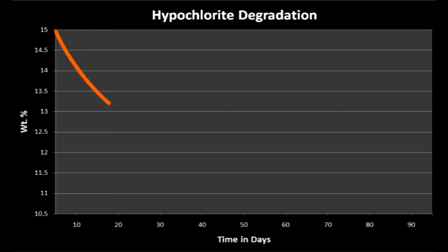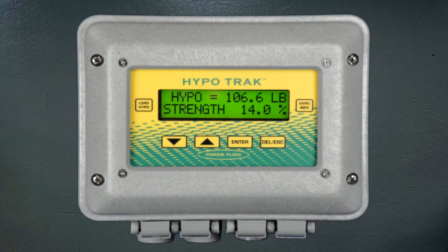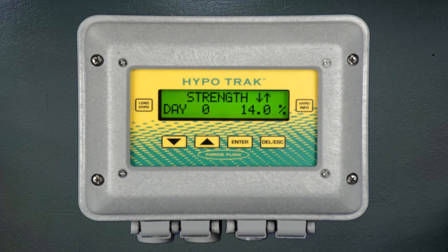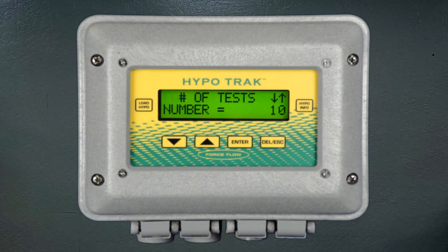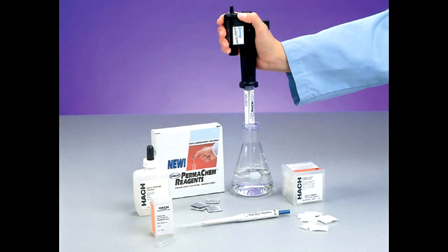As many of you are aware, Hypo is very unstable and continually degrades over time. The first unique benefit I'd like to talk about is the HypoTrak's ability to estimate the strength of your Hypo at any point in time. This is accomplished by simply entering a beginning strength and building a customer-specific degradation curve stored in the HypoTrak memory. You can store up to three different degradation curves depending on your seasonal temperature conditions. Degradation curves can have up to 10 points over an unlimited time period and are derived by using a titration kit to analyze your Hypo strength as it ages.